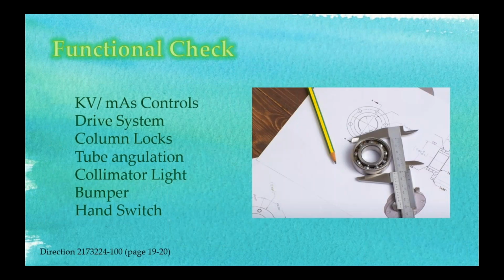Functional checks, you know, we're going to go through all the knobs. We're going to go up and down in kV. We're going to drive the system around the department. We're going to check the locks, make sure the tube goes up and down and spins around. We're going to make sure the collimator light turns on. There's usually a couple ways to turn on the collimator light, either at the collimator or on the base of the portable x-ray machine, because the tech would have to be out at the tube all the time just to turn on the light, so they have a secondary switch on the base of the portable x-ray machine. The bumper is pretty important.